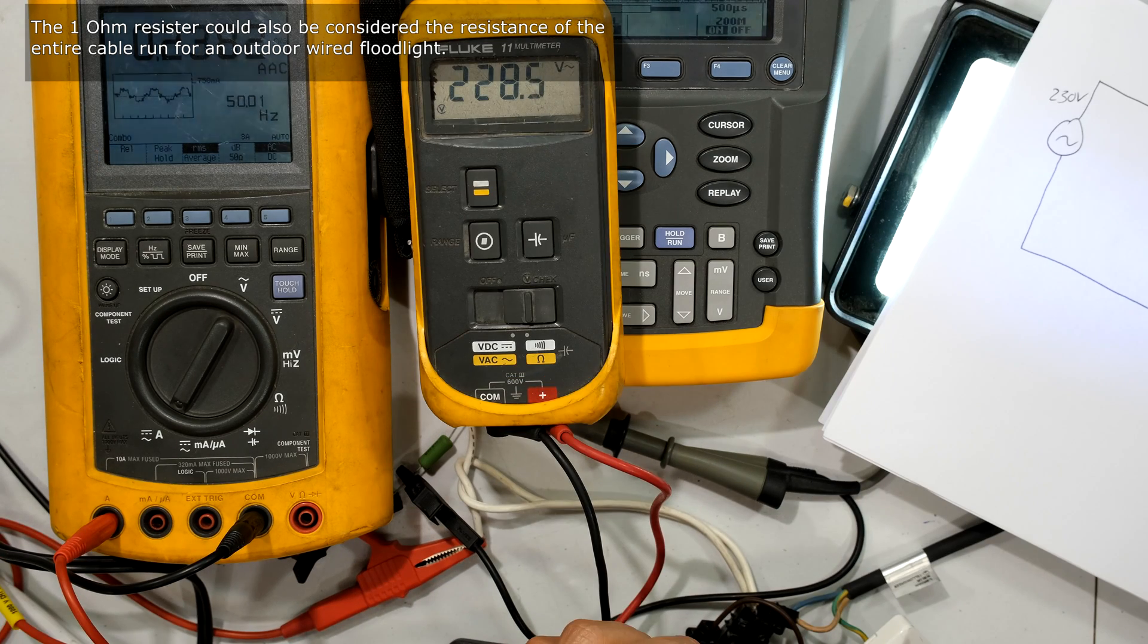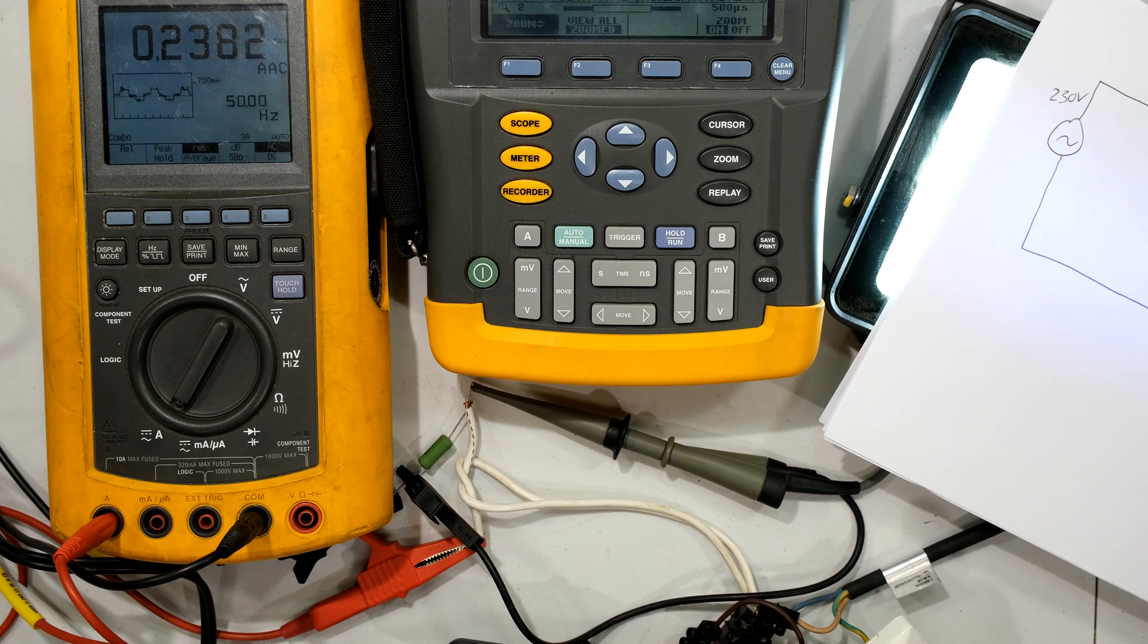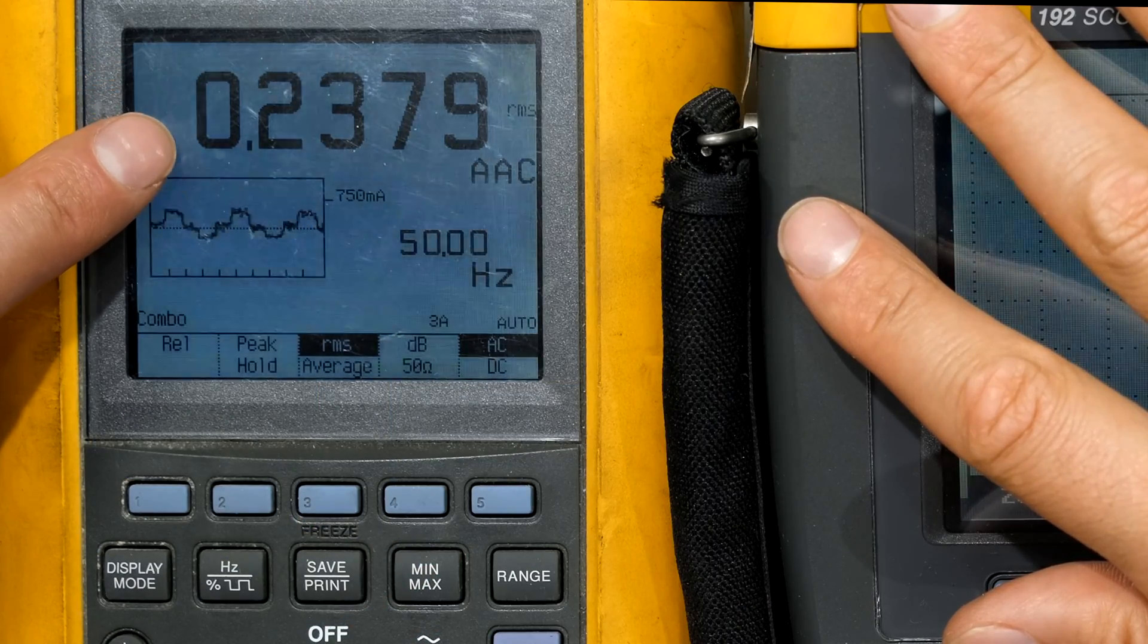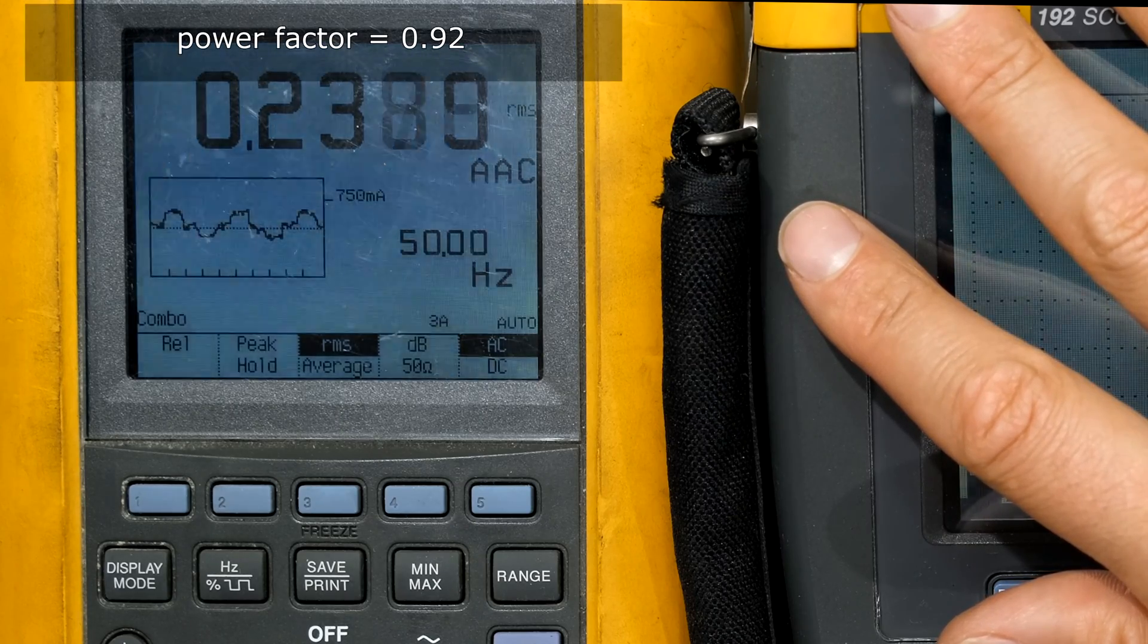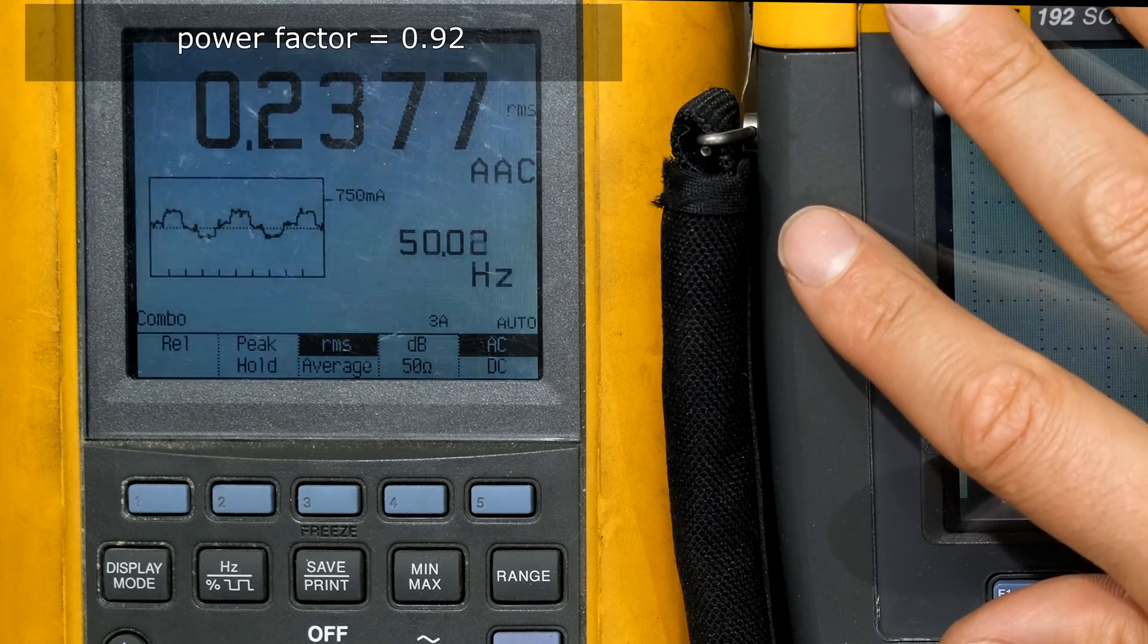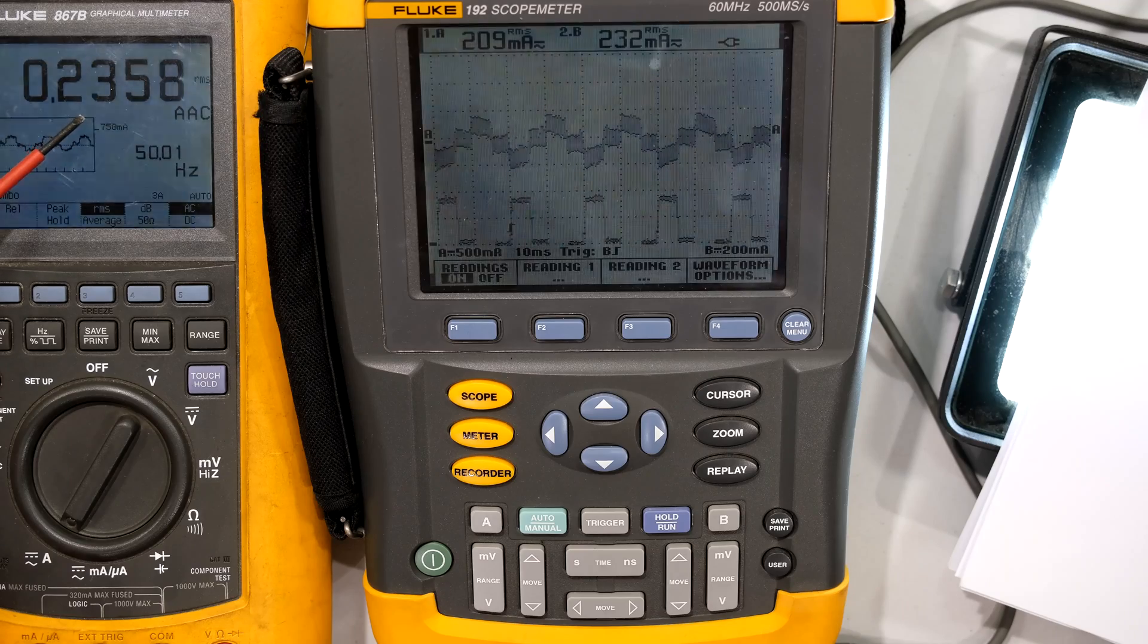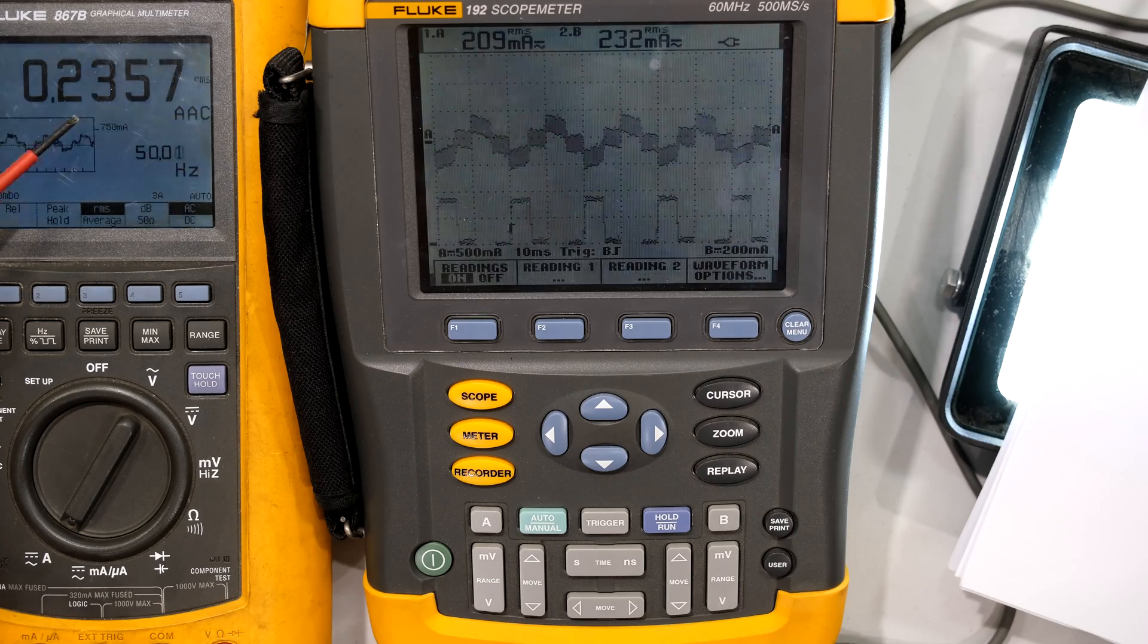Just to get a voltage reading, the voltage is 228.5 volts, so it's quite close to 230, and the light is on. The nominal AC current is 0.238 amps, so 238 milliamps for this light while it is at steady state. You can see the frequency there is 50 hertz, this is recorded in South Africa. The nominal current which I'll take as the reference measurement is 235 milliamps.